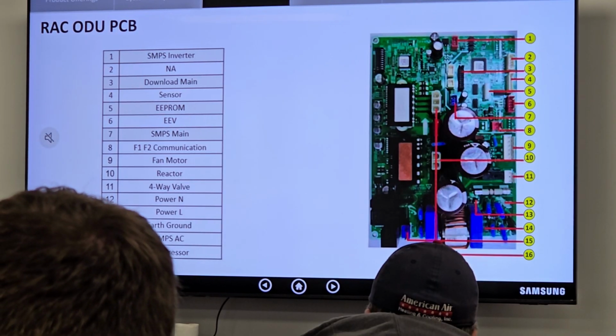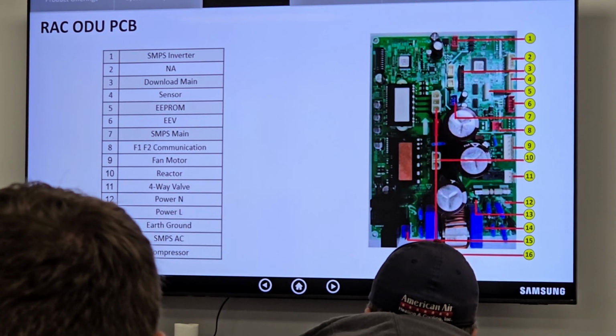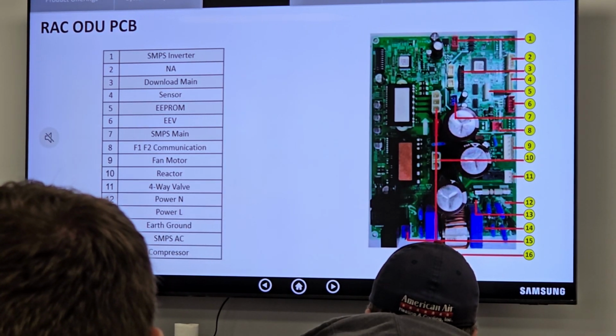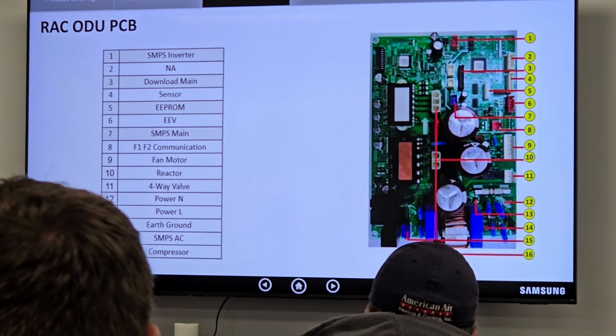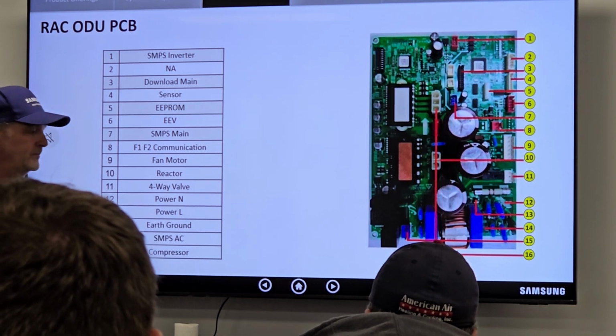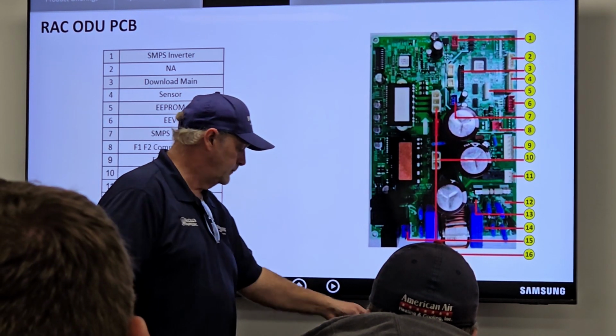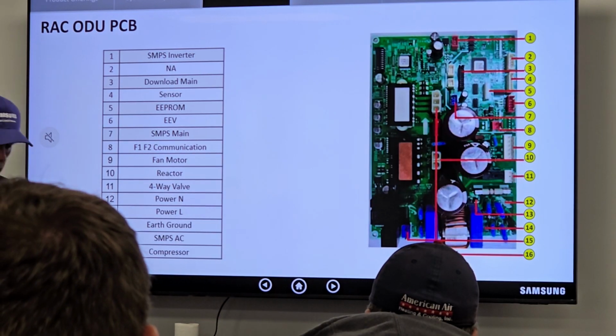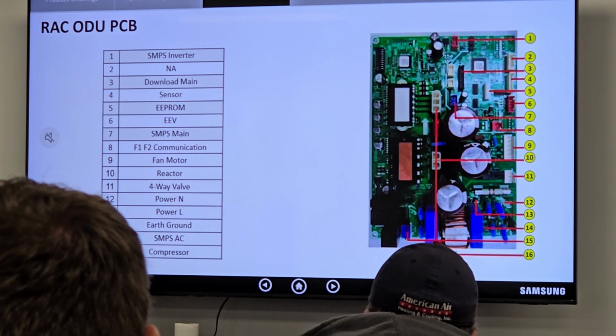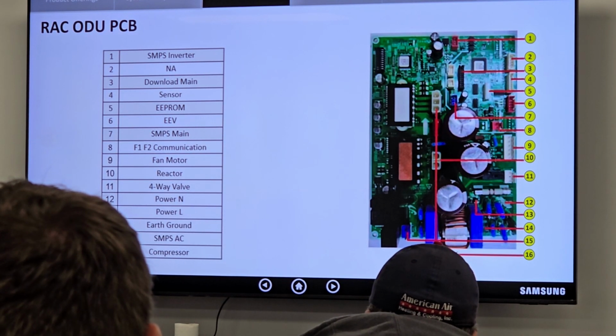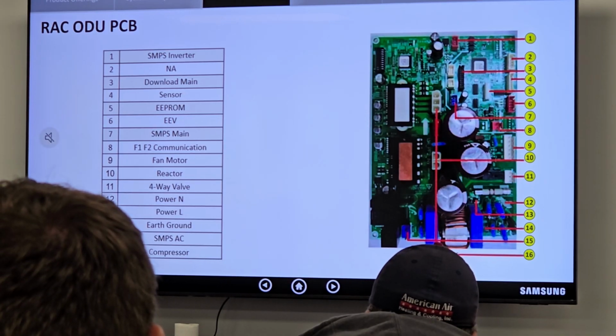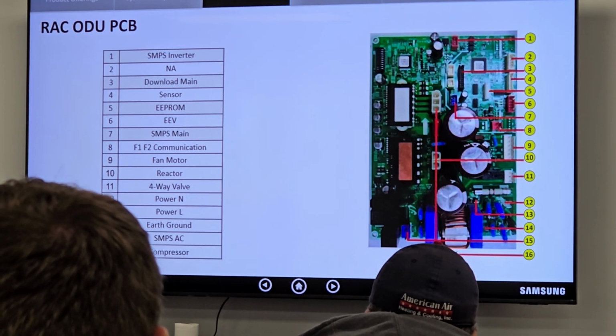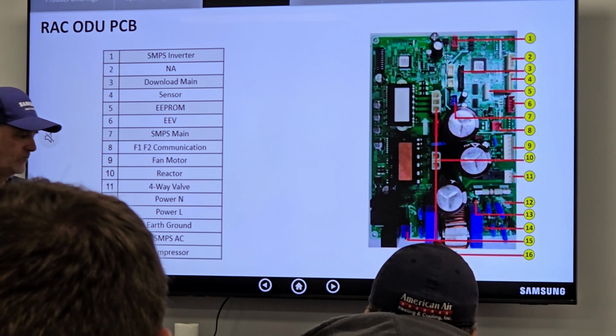If you use the shield, it may be okay, but typically we're going to use... they're probably not. Mecklenburg requires us to put the wire between the indoor and the outdoor unit in a conduit, and that would be a separate conduit for your communications. But they might not require it because they don't make us sleeve thermostat wire in commercial applications, so I'd assume we could probably just run that next to it.